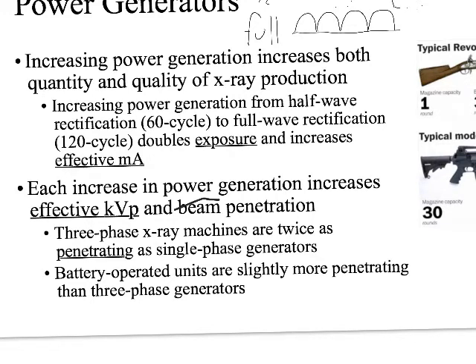Battery-operated portable x-ray machines are slightly more penetrating than even three-phase generators. It used to be that using a portable machine required reducing KVP a little because it was more powerful than the department machine. Now that's not really the case — most departments have state-of-the-art equipment. Since a battery-operated machine uses direct current, there's no need to change phases.